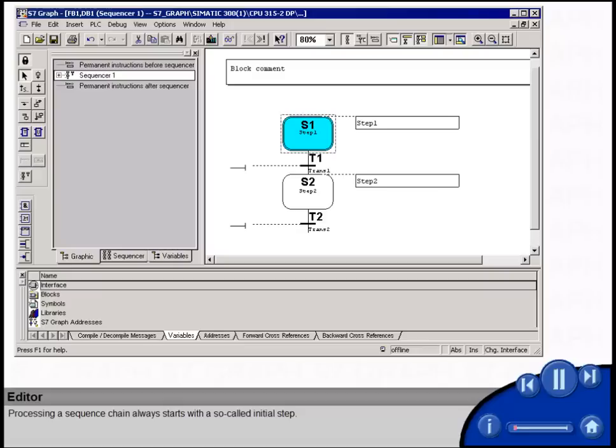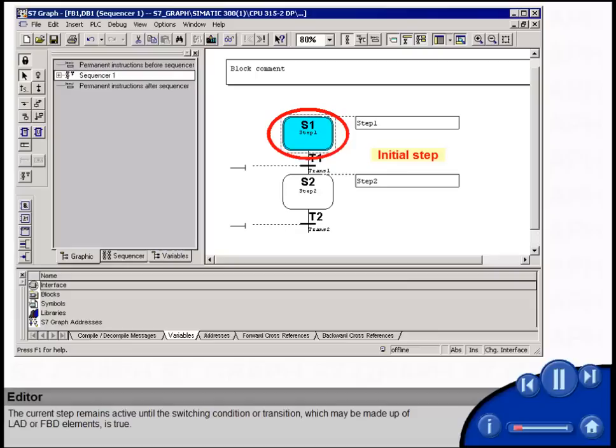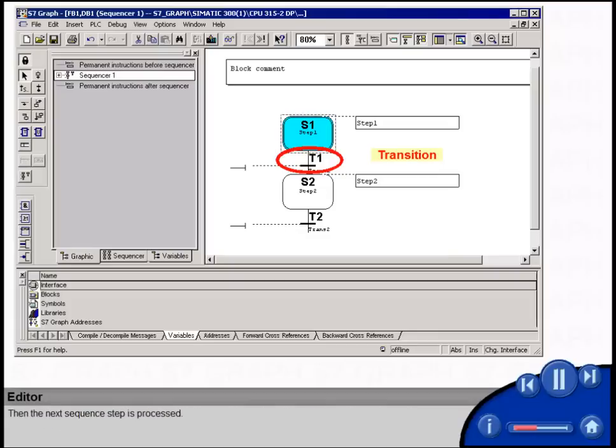Processing a sequence chain always starts with a so-called initial step. The current step remains active until the switching condition or transition, which may be made up of Ladder or FBD elements, is true. Then the next sequence step is processed.